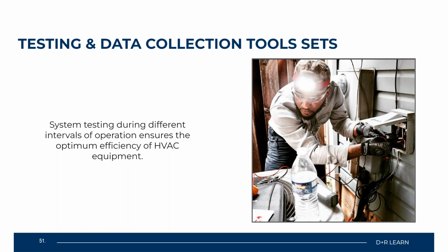It is annotated in these logbooks, so that way if there's an issue with this system, you can refer back to the logbook in order to track and see where you may have had an issue. So implementing some sort of controls systems testing plan would help you to do that. If you had control systems installed on your HVAC operation, a lot of these BAS systems are able to help you with tracking maintenance and tracking any type of services that were performed on these systems by easily scanning a barcode and checking some things off on your iPad.